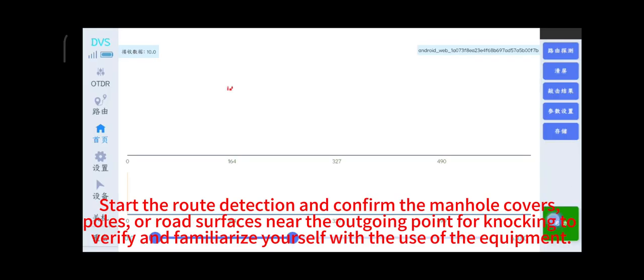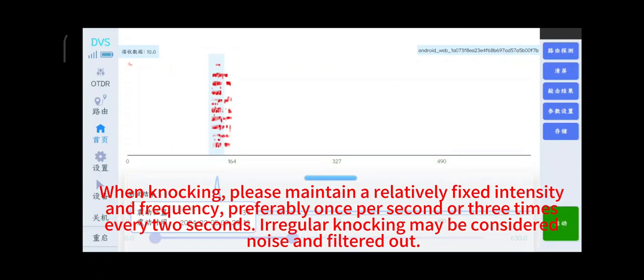Start the route detection and confirm the manhole covers, poles, or road surfaces near the outgoing point for knocking to verify and familiarize yourself with the use of the equipment. When knocking, please maintain a relatively fixed intensity and frequency, preferably once per second or 3 times every 2 seconds. Irregular knocking may be considered noise and filtered out.